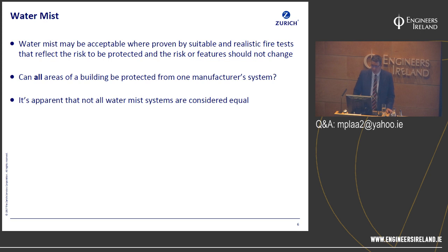So water mist may be acceptable, but it needs to be supported and underpinned by realistic fire testing and data. And by that I mean independent fire test data. Even in 2018 we're having water mist manufacturers and suppliers undertaking their own testing. I can still today hire the facility of a third-party accredited lab. I can hire the facility, I can undertake my fire test there, and the lab has no involvement whatsoever with that fire test. I can design the fire test, I can construct the fire test, I can decide what the pass and fail criteria are for that fire test, and at the end of that process I get a nice shiny document with the lab's name splattered all over it.